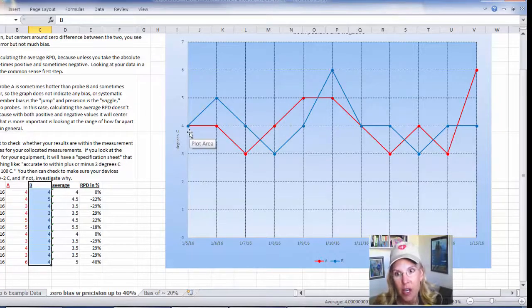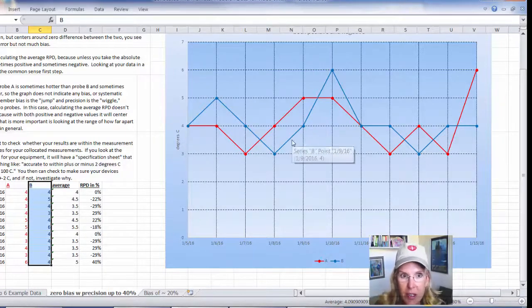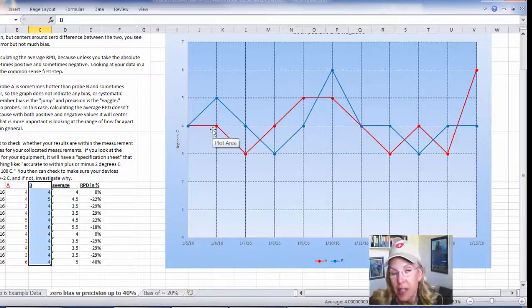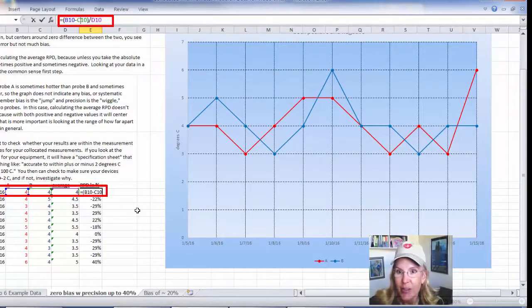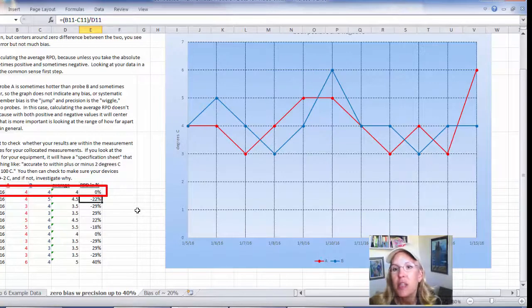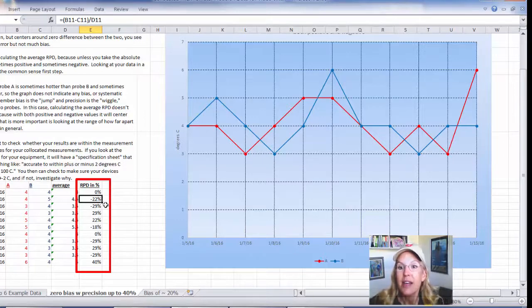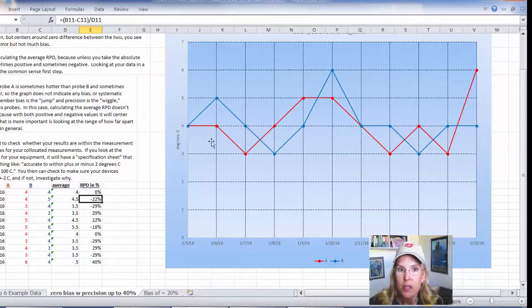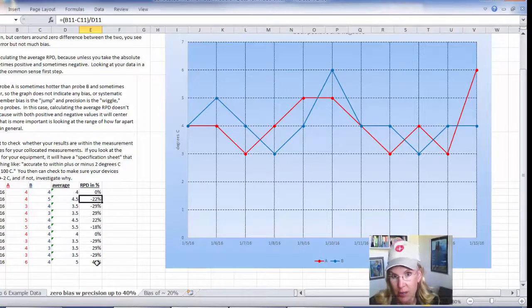This is an indicator of precision error. If you wanted to quantify this error, once you've gathered some time period of data, you do the calculations in column E. If we click in that cell, the arguments that go into that formula are shown in color, and you can see that the relative percent difference is already formatted to show as a percent. Depending on which probe is higher than the other, you're going to have a relative percent difference that's sometimes positive and sometimes negative — that's an indicator, because sometimes thermometer A is higher than thermometer B, and vice versa.